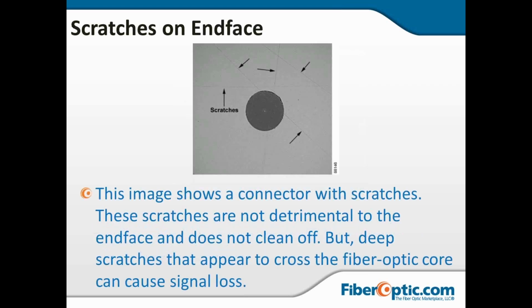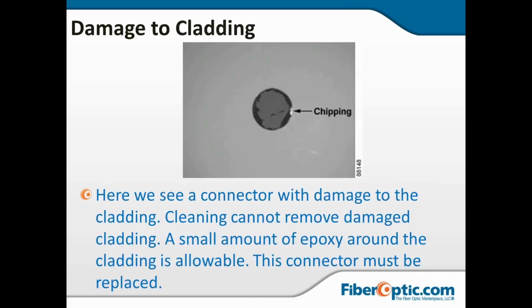Scratches. In this case, the scratches are probably not as critical as they could be. None of these scratches actually intersect the core, and this connector could probably be cleaned a little bit and continue to be used. I would double check reflections through this connector, but if you're getting high reflections, you're going to end up replacing it, but I'd give this one a shot. But just be aware that those scratches close to the core are where you're going to start getting into problems.